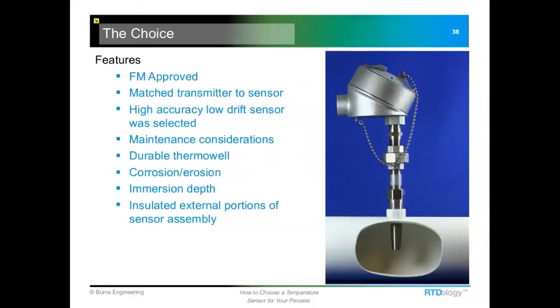And I think with that, if we have any questions, this is our final selection here. And the only thing I'm not showing is the insulation around the pipe. But I think this gives us a good, accurate temperature measurement. We can maintain it easily. The thermowell is going to last a long time. We've chosen an immersion depth that's not ideal, but we were able to make it work okay with the addition of the insulation around this section of the piping. And that's going to be a pretty good selection for what we're doing here.